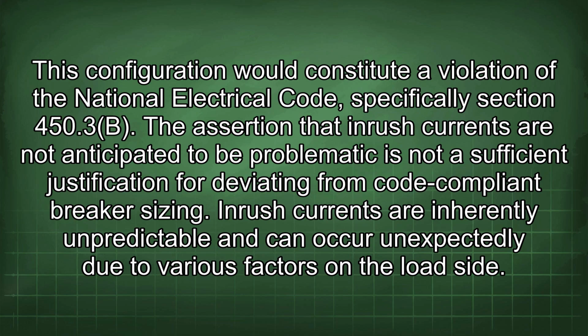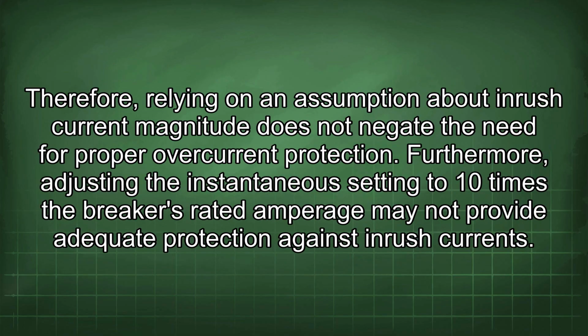The assertion that inrush currents are not anticipated to be problematic is not a sufficient justification for deviating from code-compliant breaker sizing. Inrush currents are inherently unpredictable and can occur unexpectedly due to various factors on the load side. Therefore, relying on an assumption about inrush current magnitude does not negate the need for proper overcurrent protection.